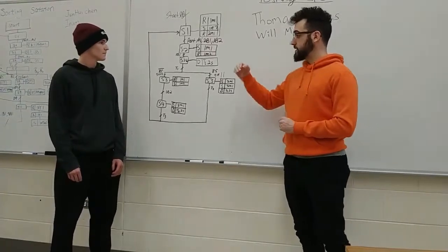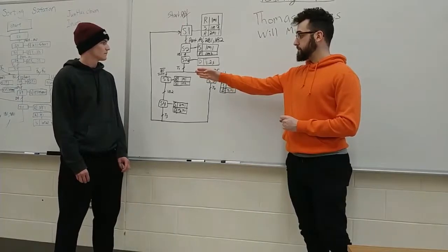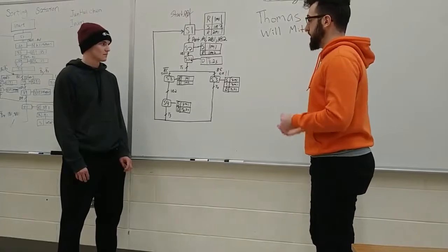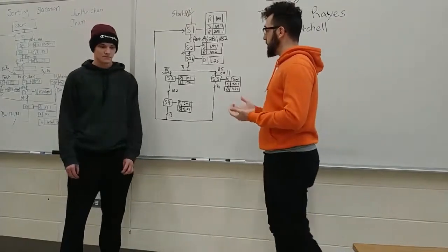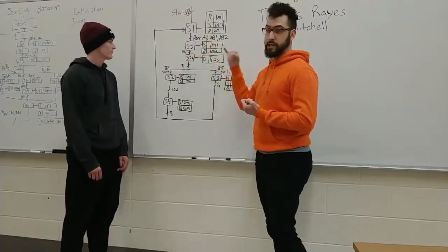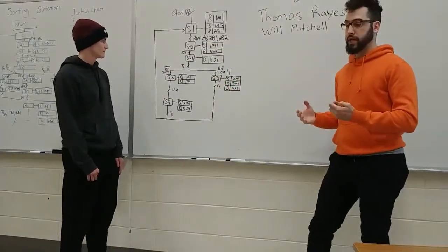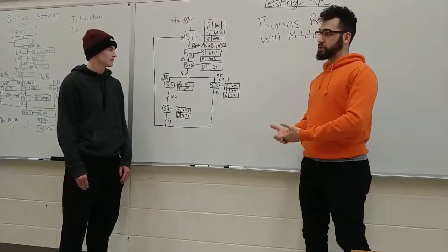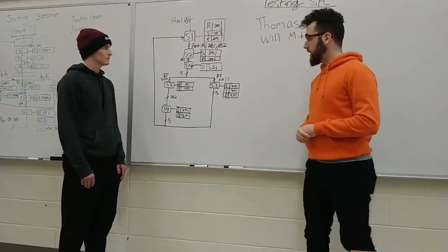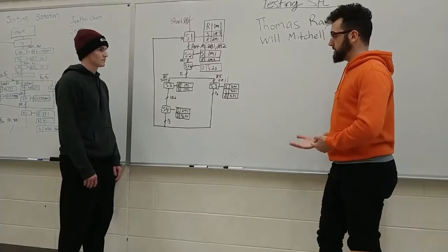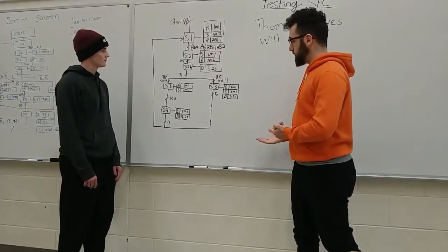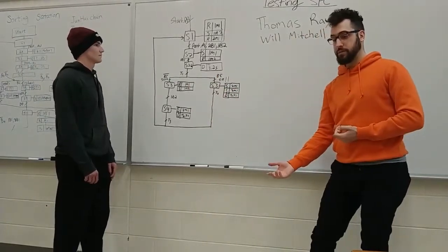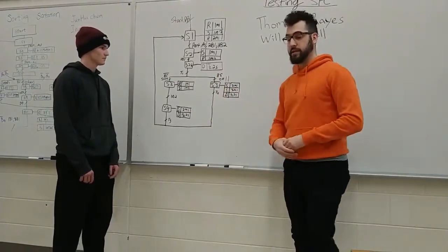B5 isn't detecting whether or not the piece is short or tall, or when the elevator lifts and it gets to the top, 1B1 isn't detecting that it's reached its point, in which case it won't allow the system to move to the next step, which would be the pusher extending. Or if it were to happen at the end of the system, that could be because of 1B2. When it's lowered, 1B2 does not detect that it's reached the bottom, and the pusher will also not extend.